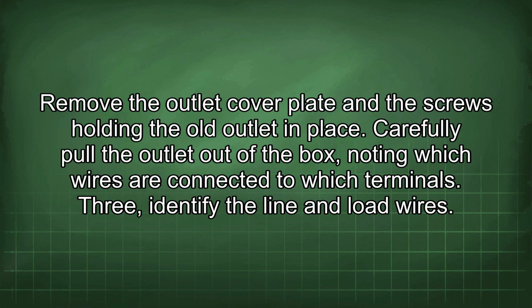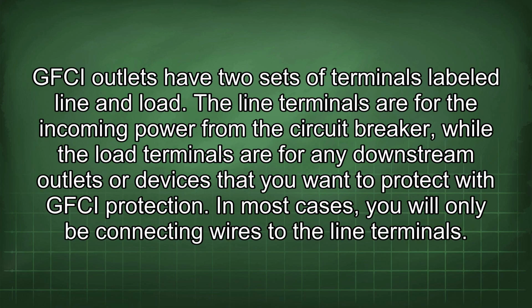3. Identify the line and load wires. GFCI outlets have 2 sets of terminals labeled line and load. The line terminals are for the incoming power from the circuit breaker, while the load terminals are for any downstream outlets or devices that you want to protect with GFCI protection. In most cases, you will only be connecting wires to the line terminals.